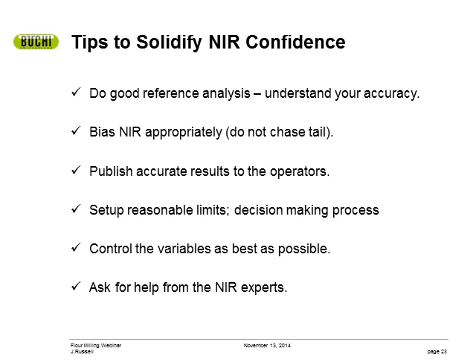One thing a customer of mine did to help with operator confidence is he put up a whiteboard next to the NIRMaster. Whenever he got the wet chemistry results back, he would show the comparison, so operators could see how accurate the Buchi had been for the last week based on those analyses. Over time, that really helped with operator confidence. You should also set up reasonable warning limits and critical limits, and have some kind of decision-making process that makes sense to the operators. Control your variables as best as possible, and ask for help from the NIR experts.